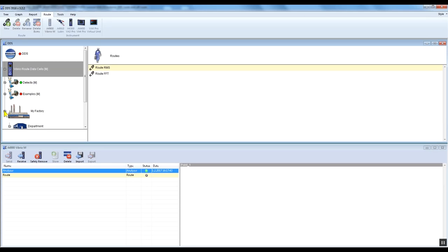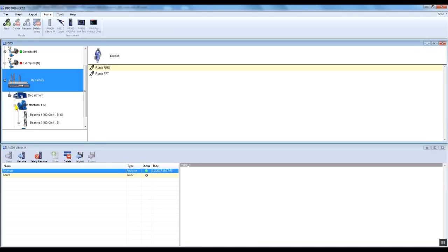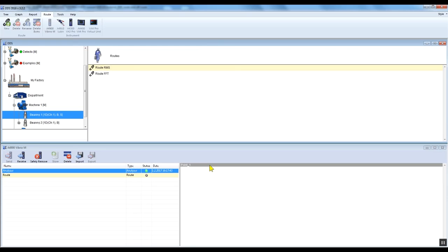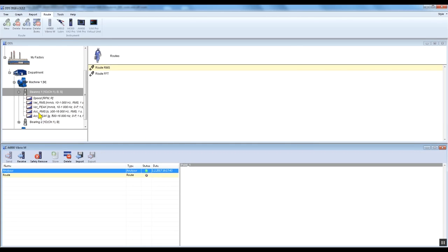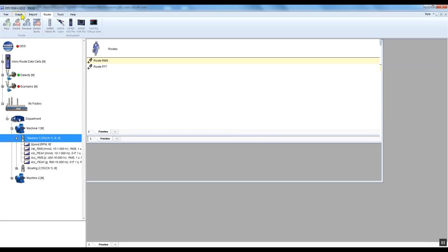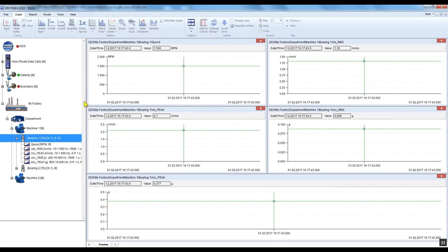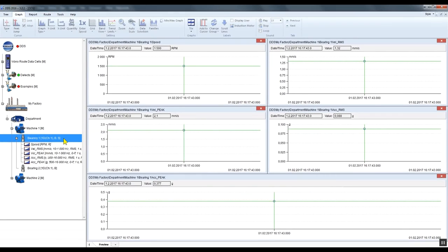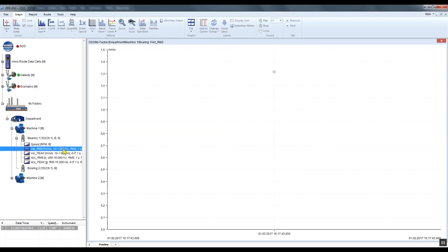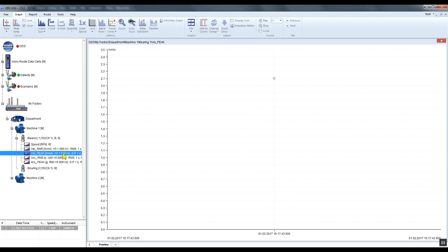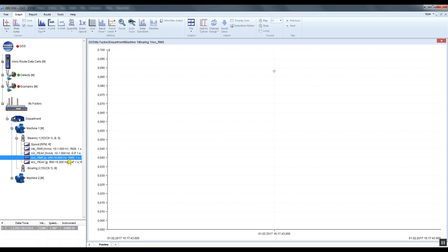The explanation is simple. We've measured off-route data, so the DDS software doesn't know where to place or store this data. To store the data, use the drag-and-drop function. Take the measurement with the mouse and place it on any part of the tree where you want to store this off-route data. I place it under bearing 1. Now I can see all the readings which have been stored under the first Vibrio M screen: speed, velocity RMS, velocity peak, acceleration RMS, and acceleration peak.